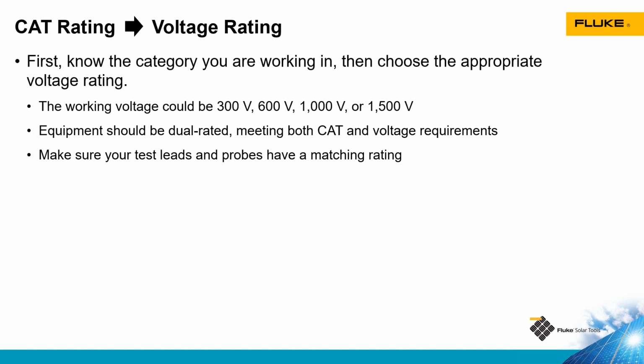And in solar, we have a wide range of voltage possibilities, everything from an individual module at 40 or 50 volts up to 1,500 volts on a utility scale system. We get AC systems that may be 208 or 240, 480, even 600 volts, or now 800 volts on the output of an inverter to a medium voltage transformer on a utility scale system.